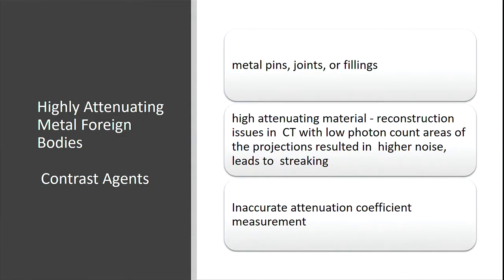So what is the problem happening here? The attenuation correction CT in most SPECT-CT machines uses a low energy CT. When the low energy CT passes through the high density material, many of the low energy photons get absorbed, leaving only the high energy photons streaking through the side of the metal. That is one side of the problem.